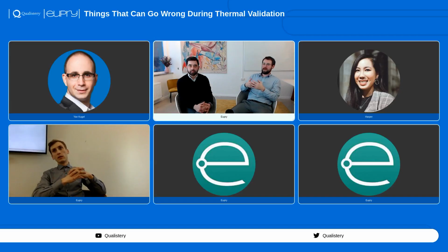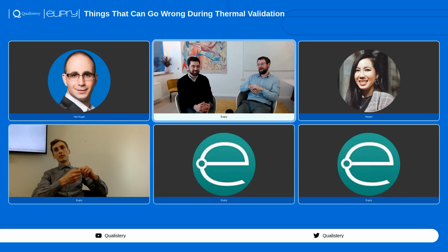A good starting point is looking at the data sheet of the sensor, where it's often written as an annual drift, maximum drift, normally expressed as one standard deviation of how all the data loggers would drift. Multiply that by 2, then you're on the safe side at 95%, and you can take that number and compare it to your limits for acceptable levels.